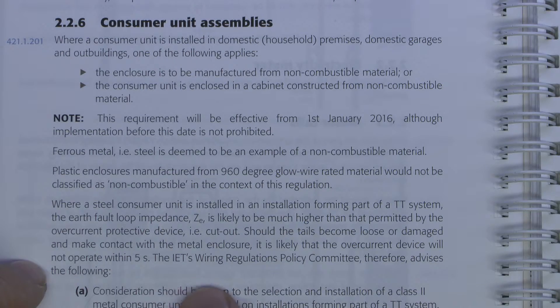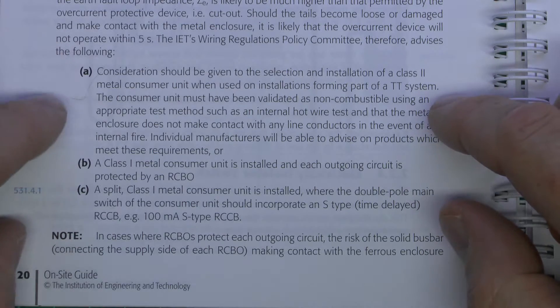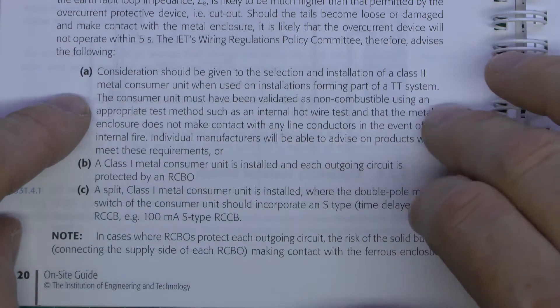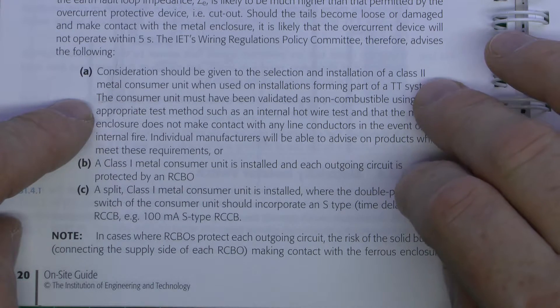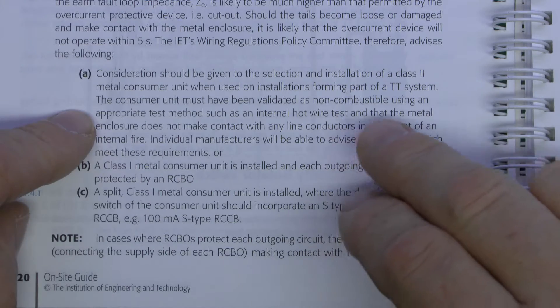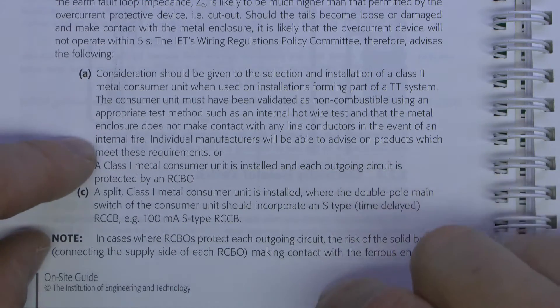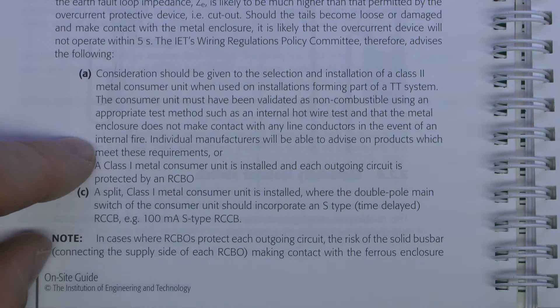As it says here, the IET Regulations Policy Committee advises the following: consideration should be given to the selection and installation of a Class 2 metal consumer unit on a TT system. This would presumably go along the line of that plastic gland assembly made by Wylex. The consumer unit must have been validated as non-combustible using an appropriate test method, and the main point being that the metal enclosure does not make contact with any line conductors in the event of an internal fire. Clearly just allowing the tails to sit where they like isn't going to be an option.